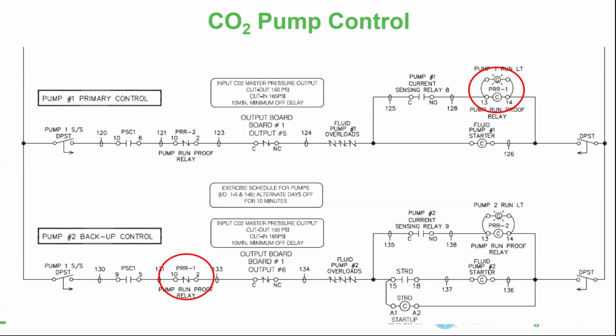So if I walk in, I see this, and then both pumps are running, the first thing I'm going to do is start looking at PRR-1 and PRR-2. Maybe the coil is bad, or the relay pins are bad, and I actually have both of them closed.